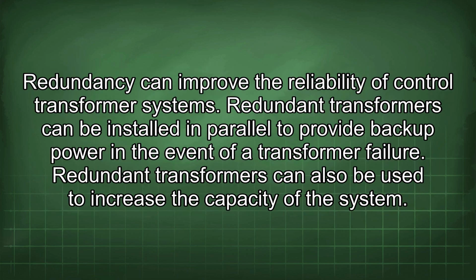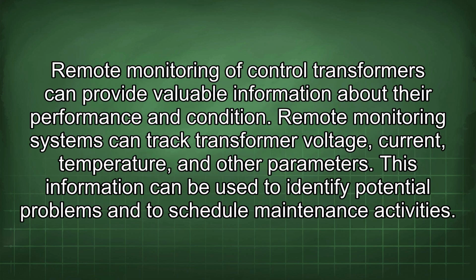Redundancy can improve the reliability of control transformer systems. Redundant transformers can be installed in parallel to provide backup power in the event of a transformer failure. Redundant transformers can also be used to increase the capacity of the system. Remote monitoring of control transformers can provide valuable information about their performance and condition.